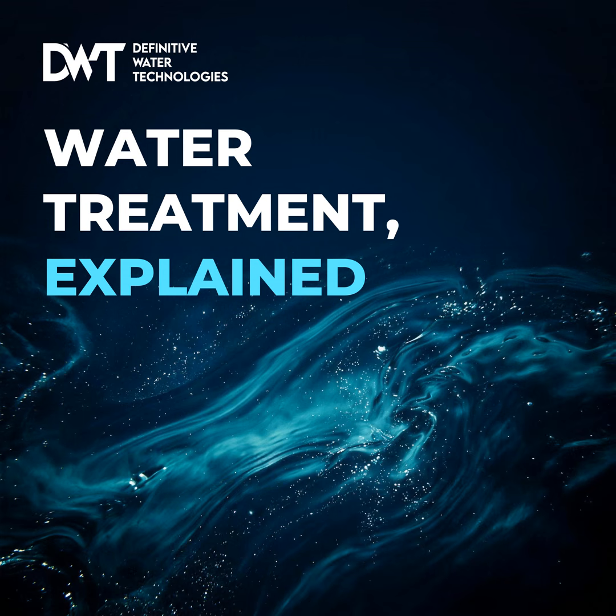The second axis is pressure, and the sources point out a trap that catches buyers. Sizing the pressure based solely on the gauge right there in the pump room. Oh, that is a classic expensive error. Yeah. You have to size the pump to inject against the real dynamic pressure at the actual injection point. So if it's 50 meters downstream or up a 3-story pipe rack, you have to add that static head pressure to your calculation, plus the tension of the spring inside the injection valve itself. What happens if you undersize it? The pump will just sit there clicking away. The controller says dosing, but the check valves will never open against that higher line pressure. It wears itself out without dosing a single drop.